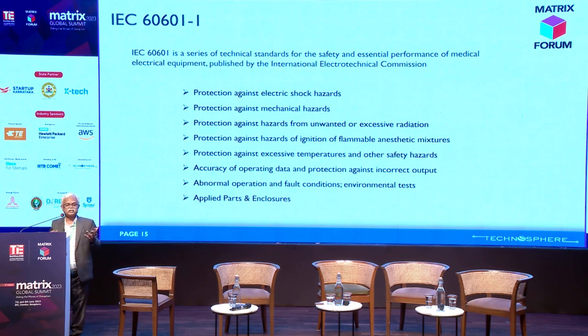Similarly, on the technology side, IEC 60601 is a standard which talks about how our device is designed to be protected against electric shock hazards and mechanical hazards. It could be a sharp edge in our design, right? So that can be hazardous, or it could be a material which is allergic to the users. So all of those aspects are to be considered when we do the development of the product.